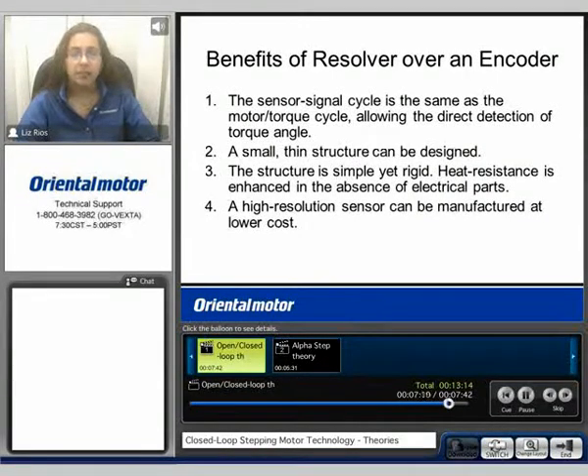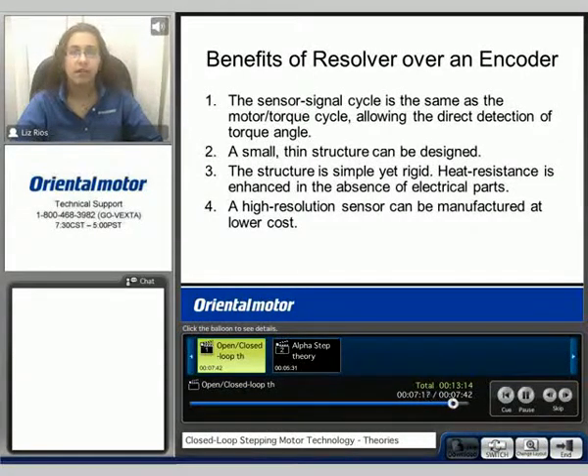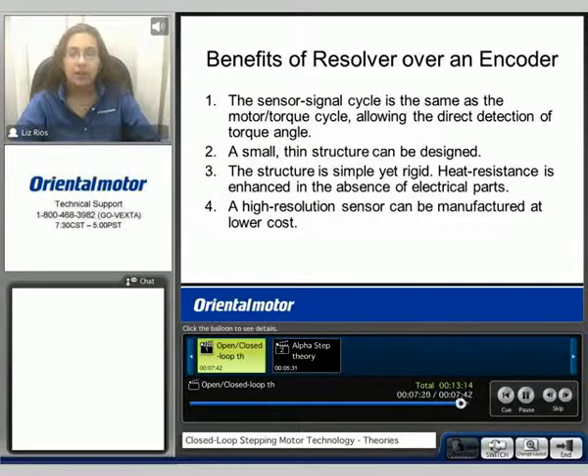Here are some highlighted benefits of a resolver over that of an encoder. The sensor signal cycle is the same as a motor torque cycle, allowing the direct detection of the torque angle. A small thin structure can be designed. Heat resistance is enhanced in the absence of electrical components, and a high resolution sensor can be manufactured at a lower cost.